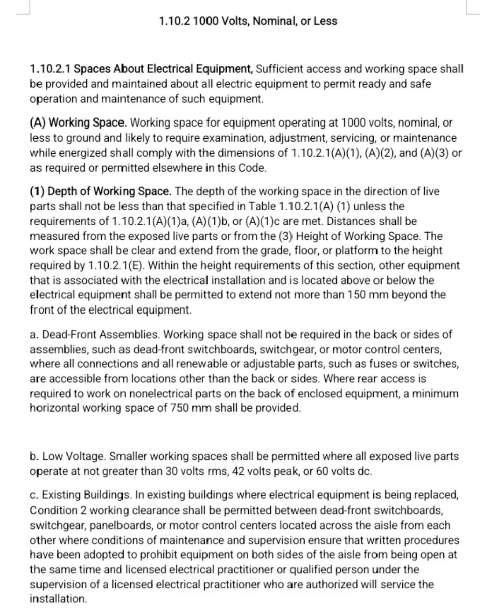A. Working space. Working space for equipment operating at 1,000 volts nominal or less to ground and likely to require examination, adjustment, servicing, or maintenance while energized shall comply with the dimensions of 1.10.2.1 A1, A2, and A3 or as required or permitted elsewhere in this code.